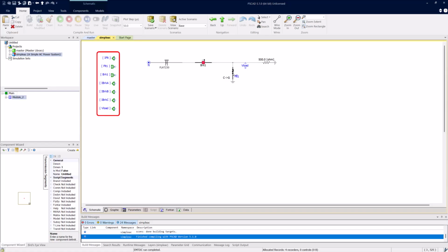If you look closer, you will see that PSCAD has generated import and export components, or tags, which automatically map and transfer the wireless signals, including the breaker signal, which crossed the boundary of the selection when the module was created, and now safely transfer data and signals into and out of the module. In addition to these, the algorithm has also generated an X-node component to provide internal connection to the electrical port generated on the module component.